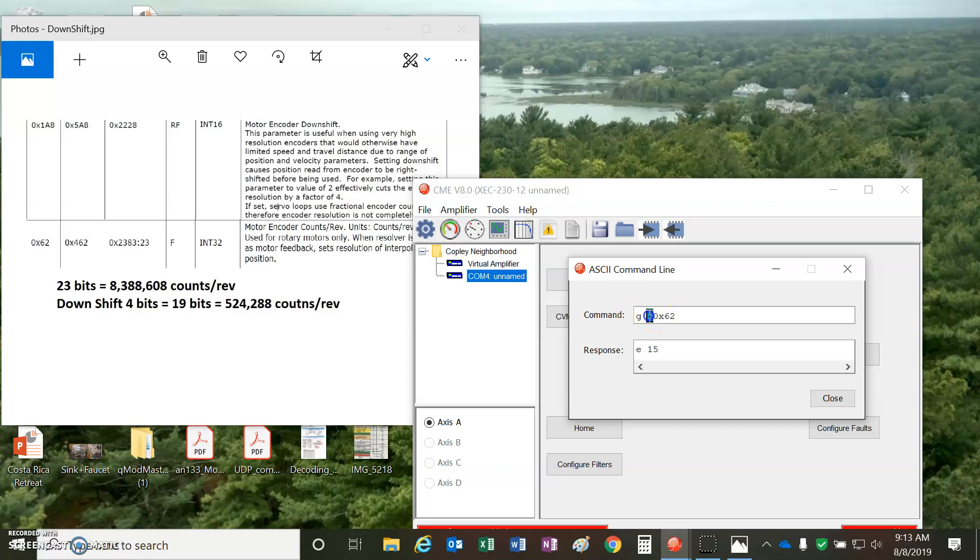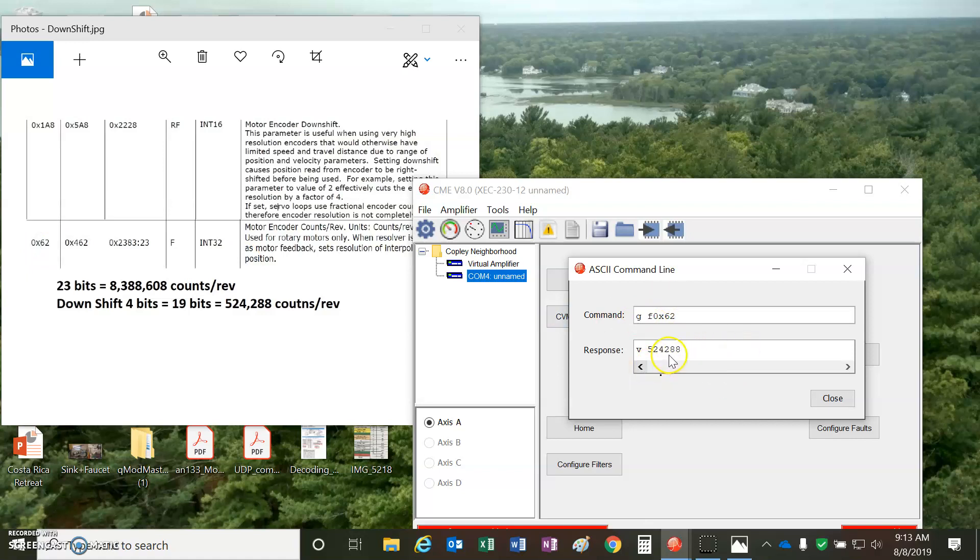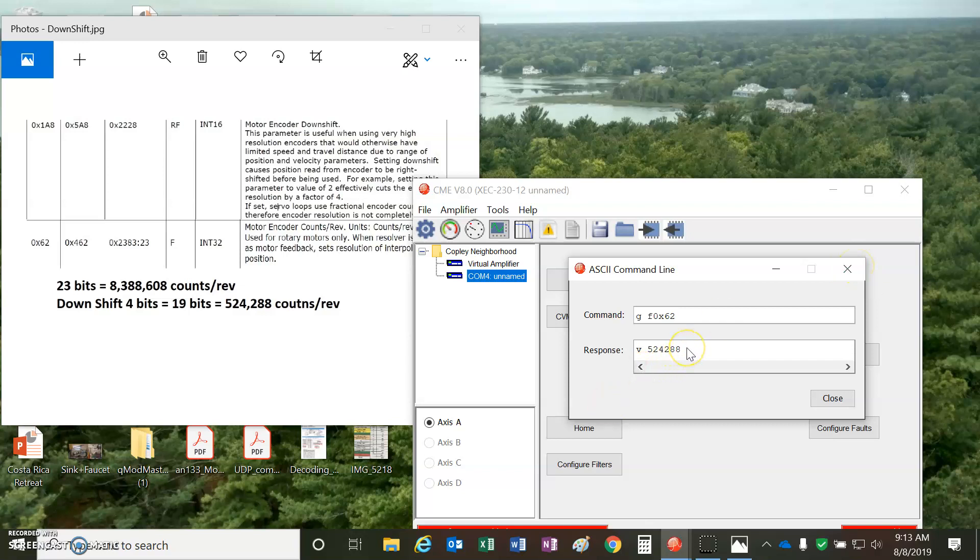And then the other parameter, well, the counts per rev, 0x62, that's not in RAM, that's only in flash. But you can see I've set the counts per rev. This allows the position loop to be closed at the correct counts as set by the downshift. So we can tell it what it is because that's the data that's coming from the encoder.